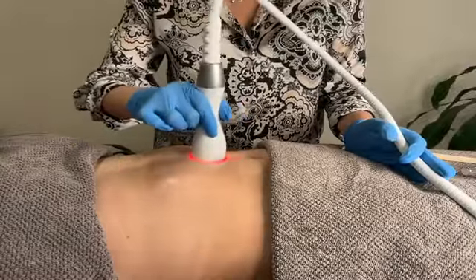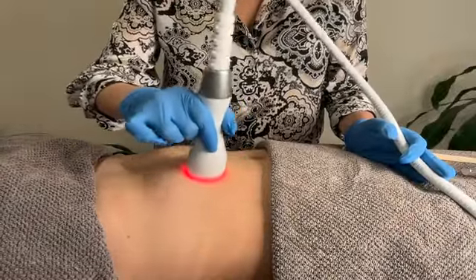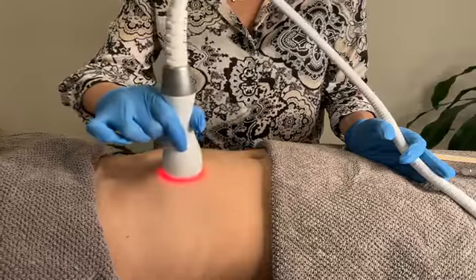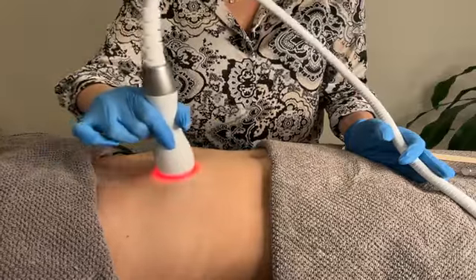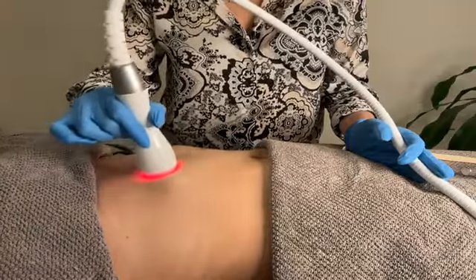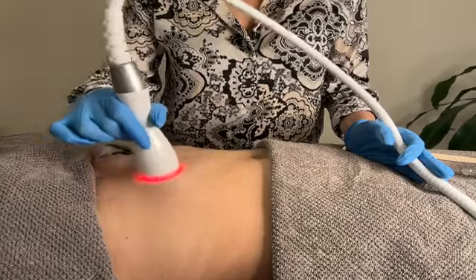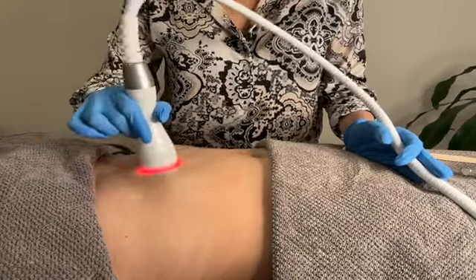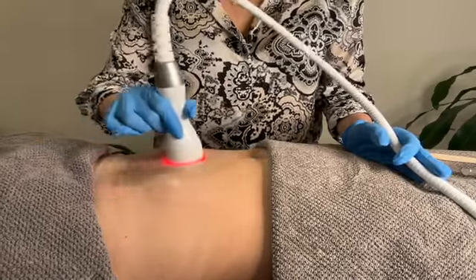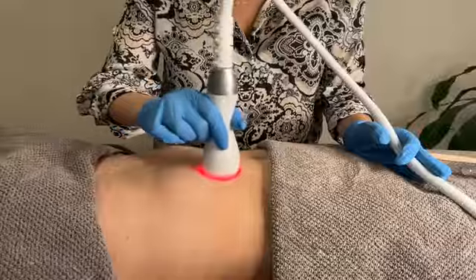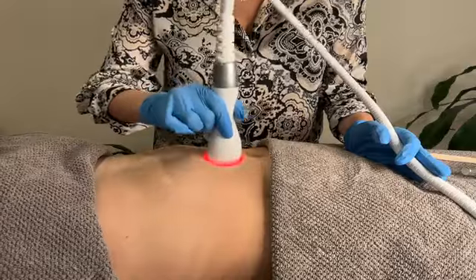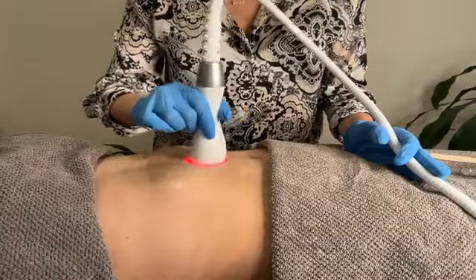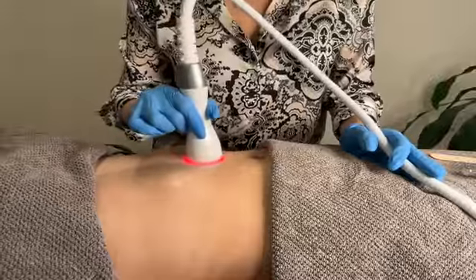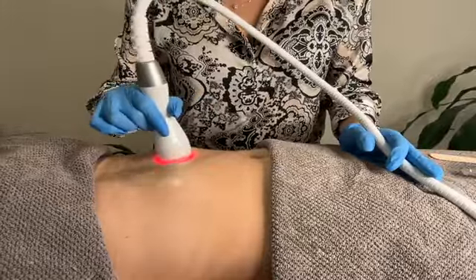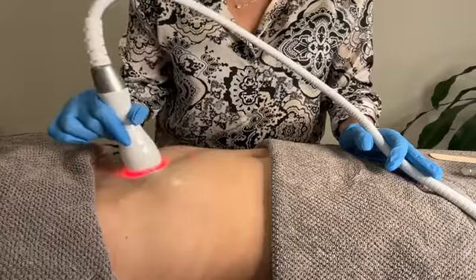So initially, what we're wanting to do is we're wanting to do really, really slow and deliberate circles. So we're really heating up the skin. So right now, my device is telling me that I'm on 33 degrees, which is way too low. And we'll keep creating these tiny little circles. The slower I move, the more heat we're pushing into the skin.